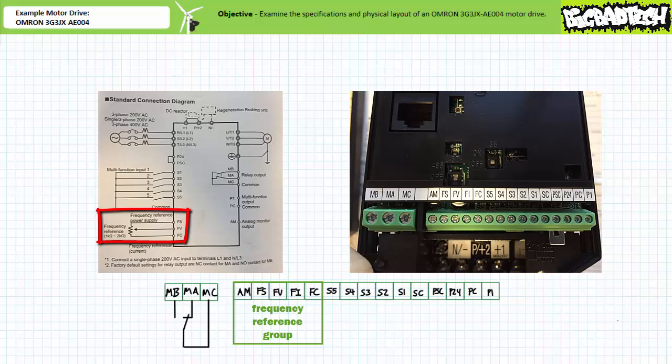As the position of the external speed potentiometer is changed, so too will the analog voltage input signal at the FV terminal. FI is an alternative frequency reference input that rather than using analog voltage signal from 0 to 10 volts, it's anticipating an analog current input from 4 to 20 milliamps. Additionally, the frequency reference group also includes an analog monitor output, AM. Depending on the program function, AM can provide a proportional representation of either the frequency or the current output by the drive.